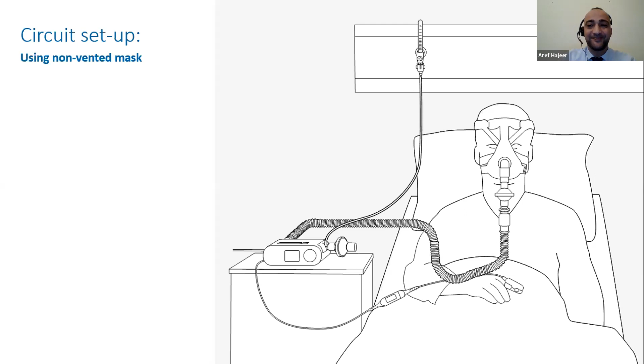That was because of the lack of ventilators available and the huge number of patients who need ventilators. So if you allow me to share my screen, we have come up with one solution to solve this, and I can show it here. So what we did between the interface and the whisper swivel, which is here, was add a bacterial viral filter. This helps to filter the exhaled air coming from the patient before it goes to the room air. It was a really good solution, and it decreased the danger of the patient's exhaled air getting into the room air. I don't know if this adds value, but I think it's good to mention.